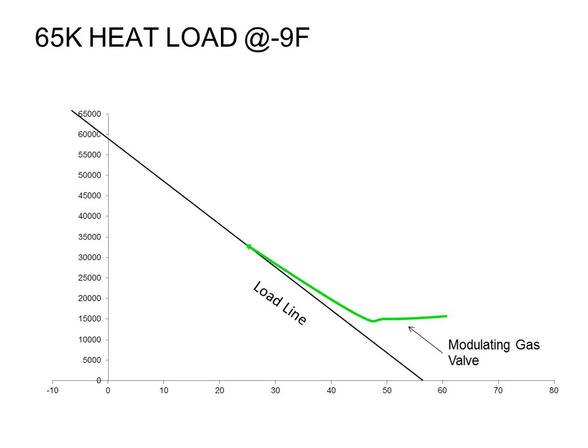Now, a couple things with that. One is that this furnace, in many cases, is not going to shut off. It's going to run continuously all winter long. There's only 3 times that the furnace should be shutting off. One is if it keeps getting warmer and warmer outside, I move down the line, and eventually I get less than 40%, which is my minimum gas valve.